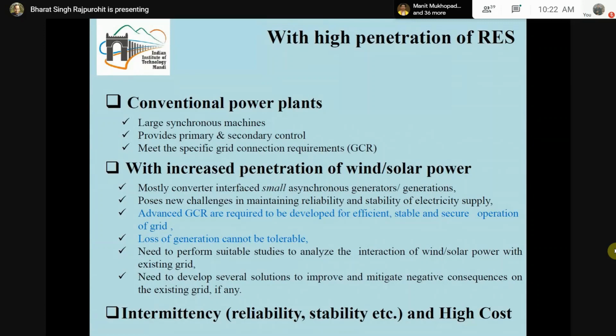Whenever we have a very big synchronous machine and it is to be replaced by thousands of generators, then we have to see how these thousands of smaller generators would be able to address the grid codes, which earlier were met by a single large synchronous machine. That is one of the challenges. When the penetration of wind and solar was very small, such expectations were not there. If there was some issue in the grid, an abnormal condition, such generation, which was very small in penetration like wind and solar, could simply get disconnected from the grid, and the role of maintaining the primary and secondary control was easily taken care of by the large synchronous machines.